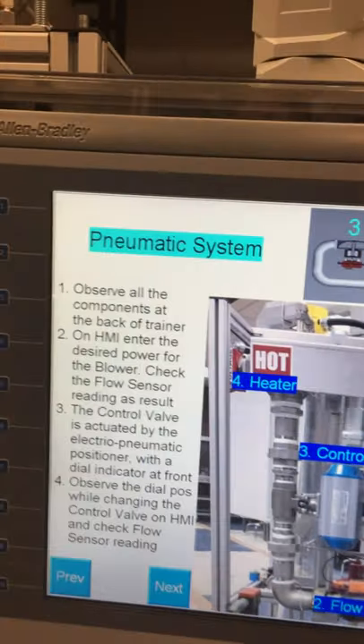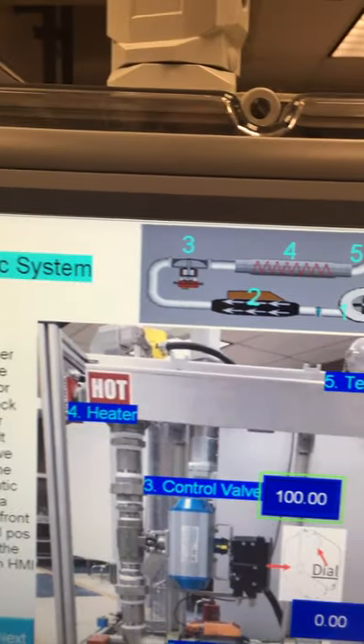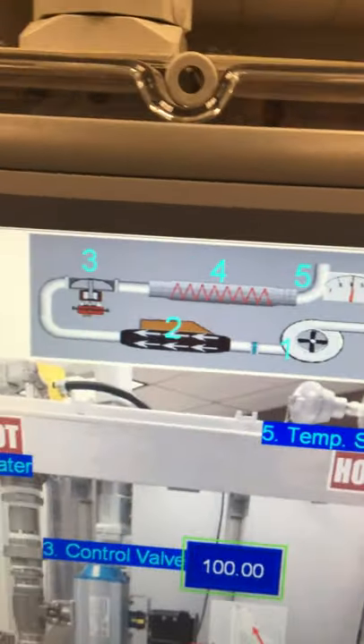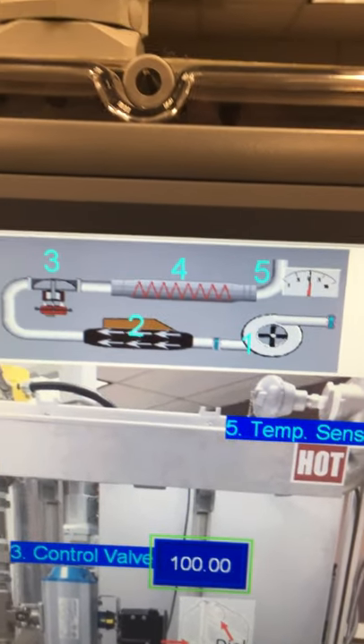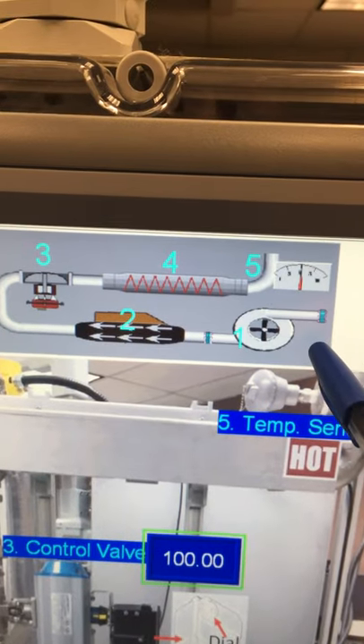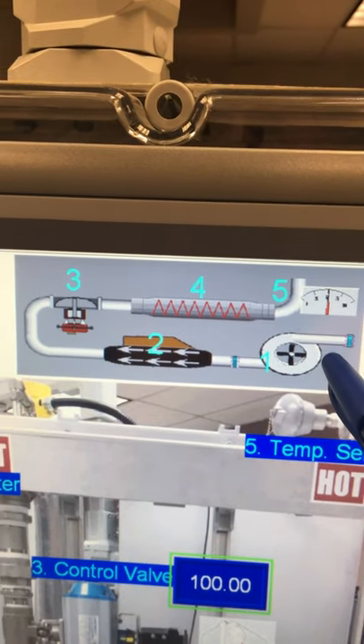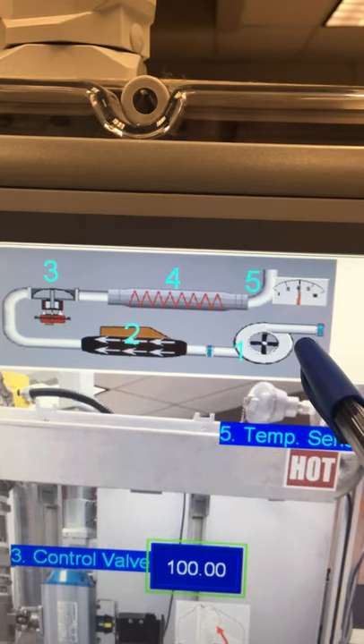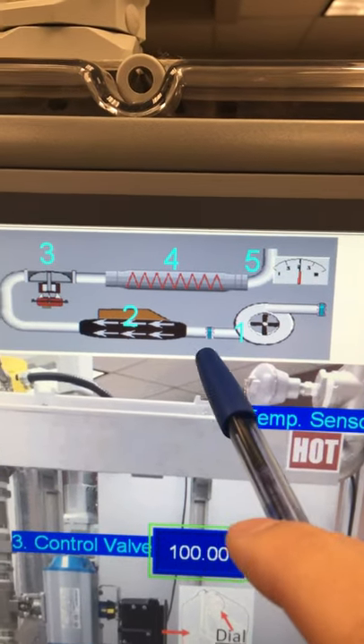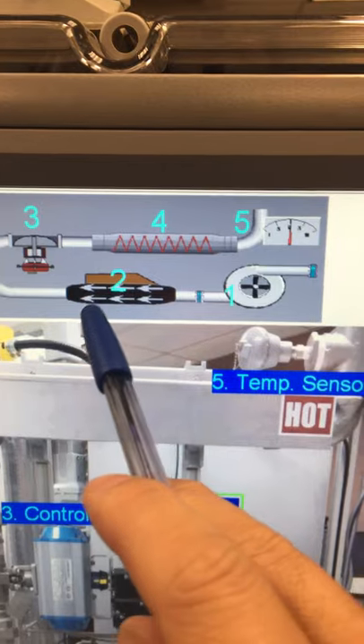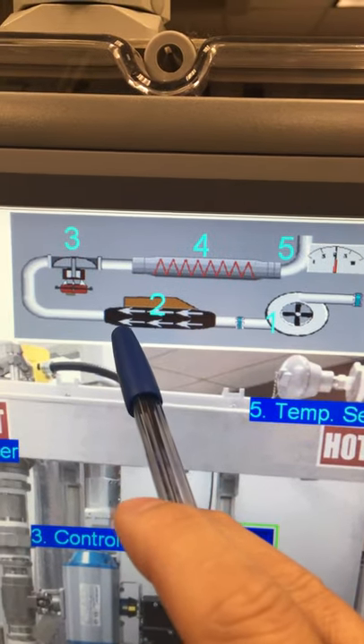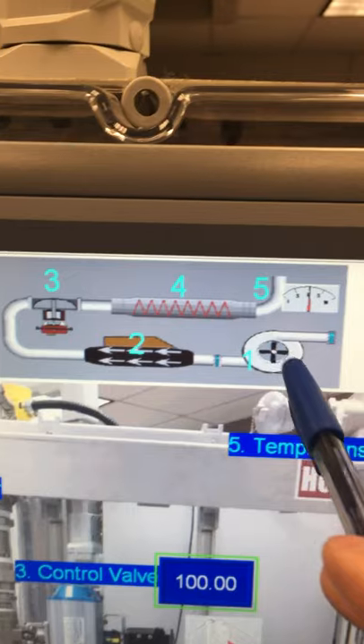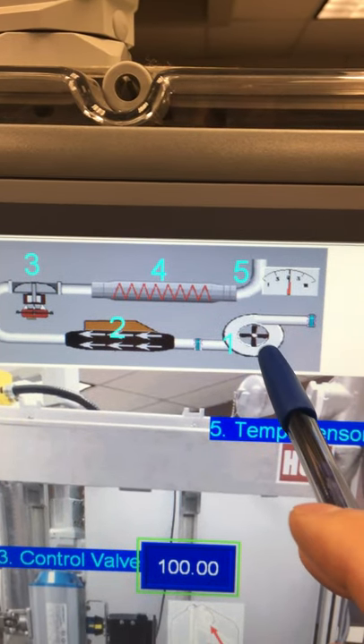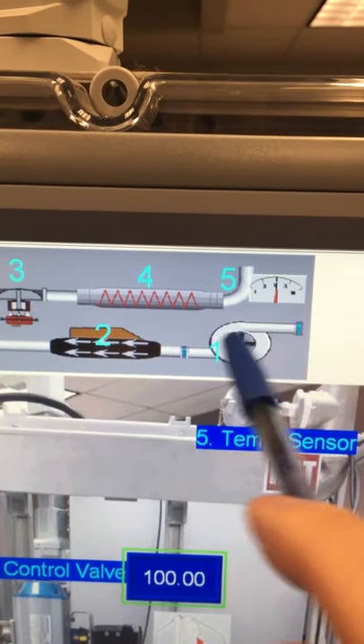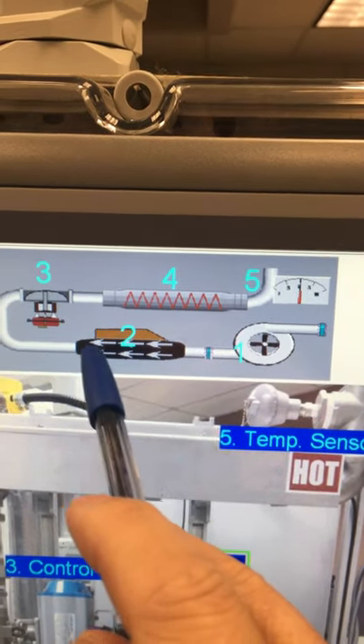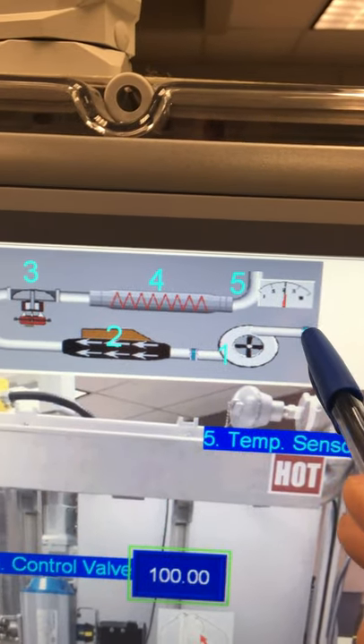On this screen, we're seeing the pneumatic system. On the trainer, we have a few devices connected together. First, at the top, the diagram shows you the pneumatic system. But there's an error on this diagram. I haven't changed it yet. The direction of the air is supposed to be opposite. Number one is the blower. The blower blows the air out, so that's why the direction is wrong. The air will actually flow this way, going through the blower.